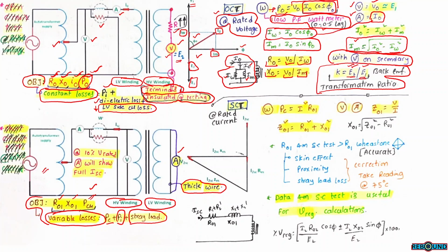As we are conducting the short circuit test, the full short circuit current can flow through the circuit by applying only 10% of rated voltage, because we are applying this voltage on the HV side. So by applying 10% of rated voltage, full load short circuit current will flow through the circuit. The ammeter will read the current, the wattmeter will read the total copper losses, and the voltmeter will measure the voltage across the HV terminal. The short circuit test is conducted with reference to rated current.